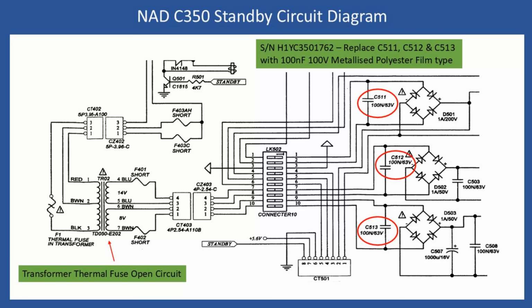Over time the capacitors fail, going short circuit, which results in excess current being drawn from the standby transformer. Then the internal thermal fuse goes open circuit and the amplifier no longer operates, and there's no direct replacement. What I hold in stock is a small toroidal transformer which can be used to replace the standby transformer. Replace the high frequency filter capacitors too, and in virtually all cases you can restore the amplifier back to operation.